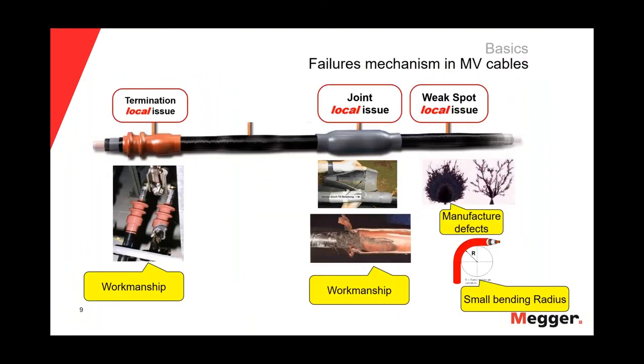In terms of the failure mechanisms for medium voltage cables, we should distinguish between local issues and global issues. Local issues will affect only a small portion of the insulation or some accessories in the cable — it could be splices or terminations — but local issues will not be spread along the entire segment of the cable. Mainly, local issues are related to workmanship issues or manufacturing defects.